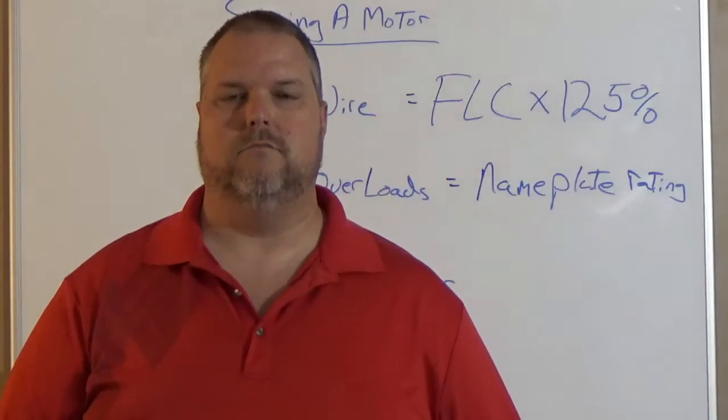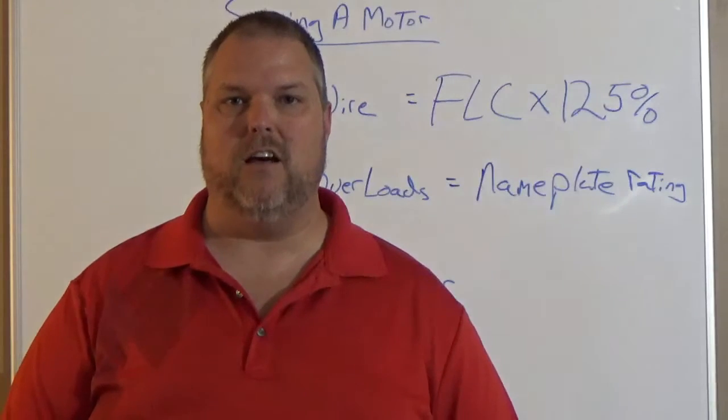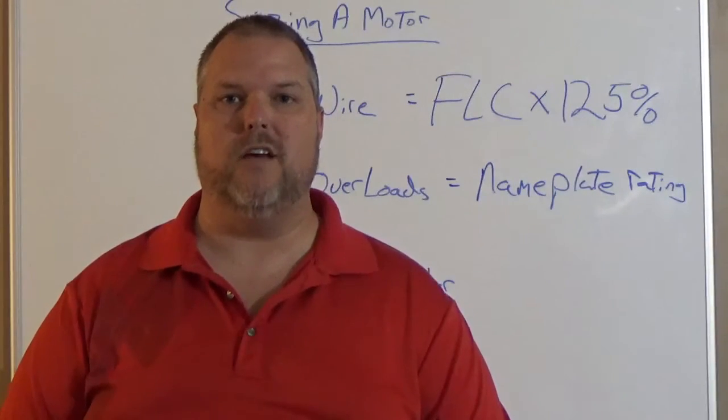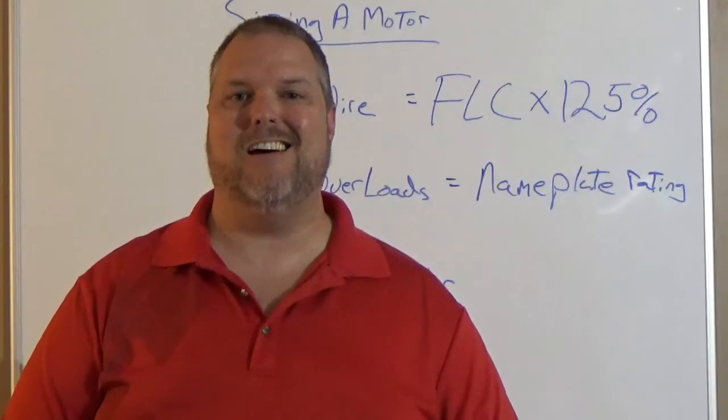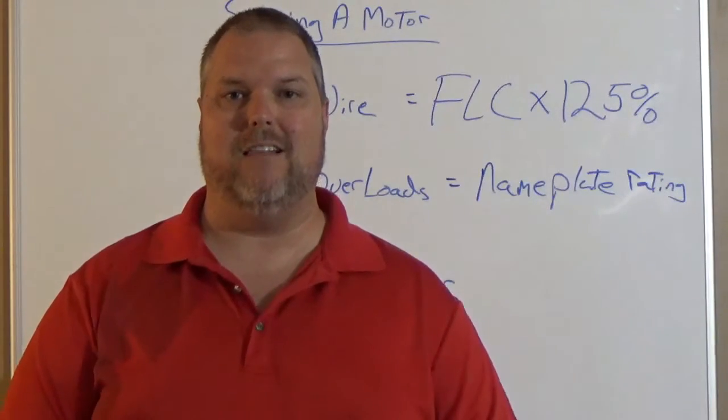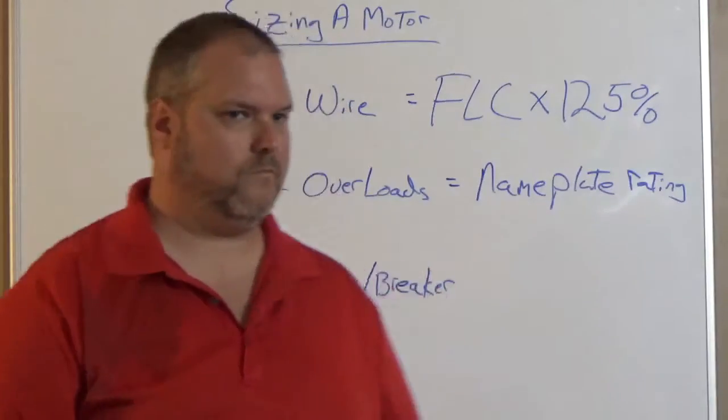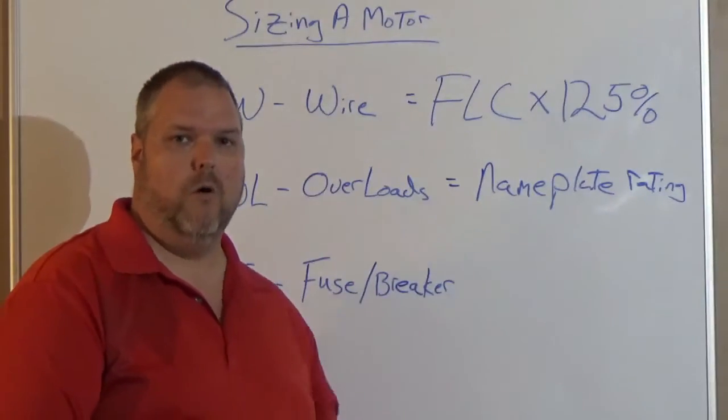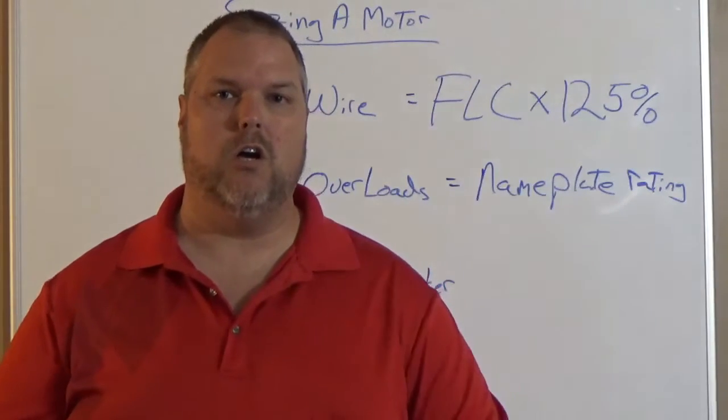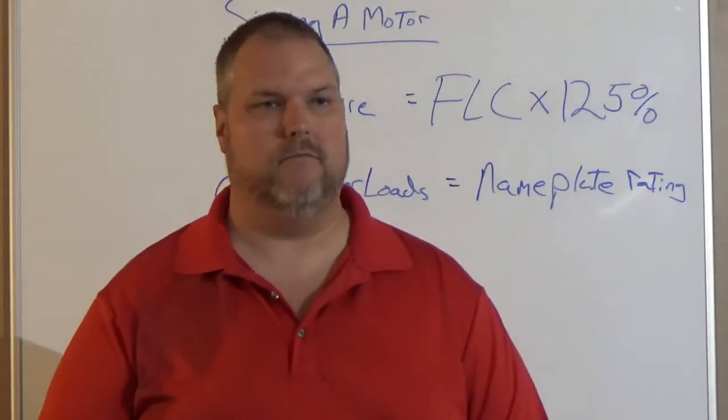Now we have to size the fuse. Where would we find this? We're going to have to go to article 430.52, and that is going to tell us all our information. It's basically a little table that's going to tell us what type of fuse or breaker are we going to be using, what type of motor are we going to be protecting, and it's going to tell us where it goes. As we go through the examples, I will show you in the codebook exactly where it is so you can highlight your codebook so that when it comes time for you to actually size a motor, you know exactly where to go.